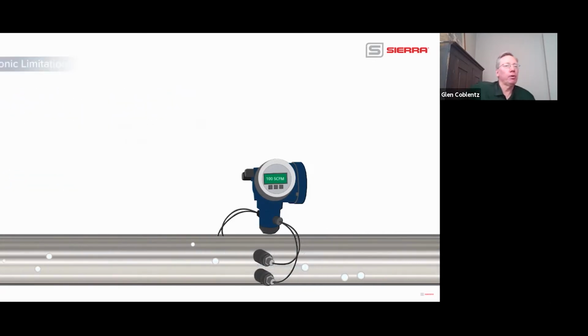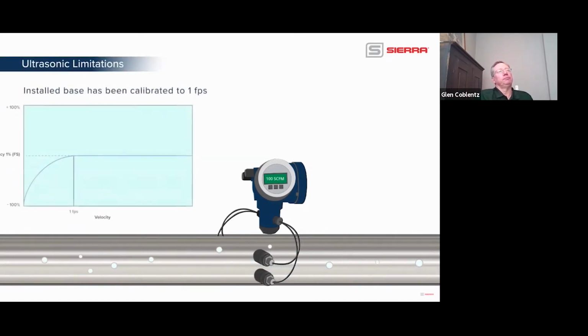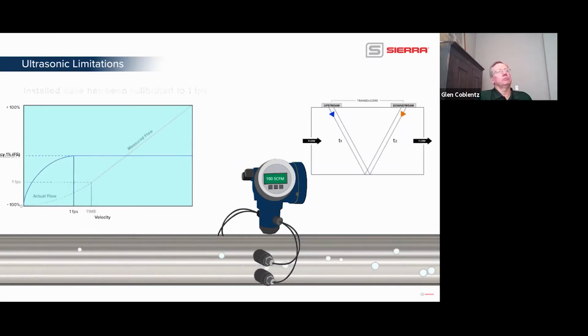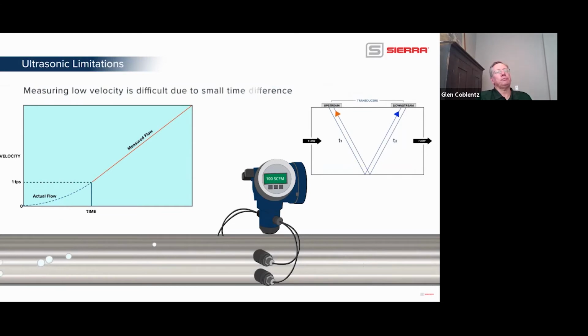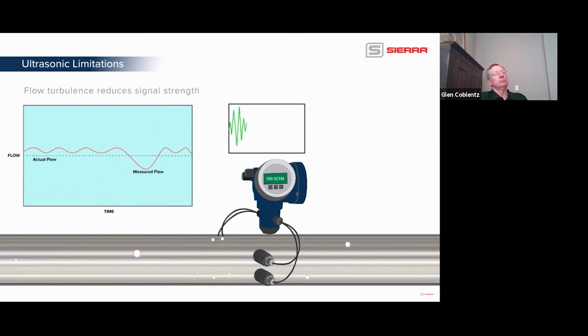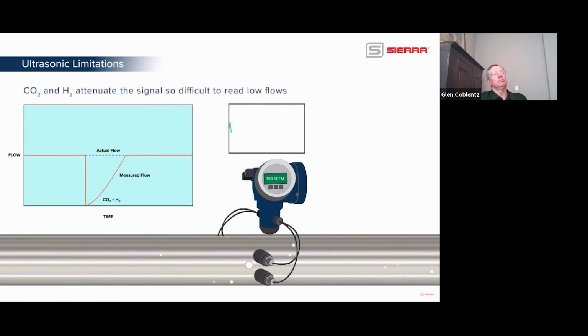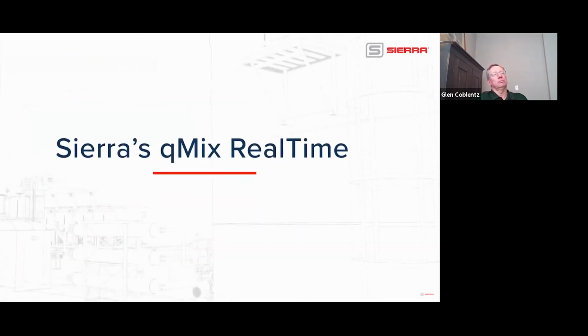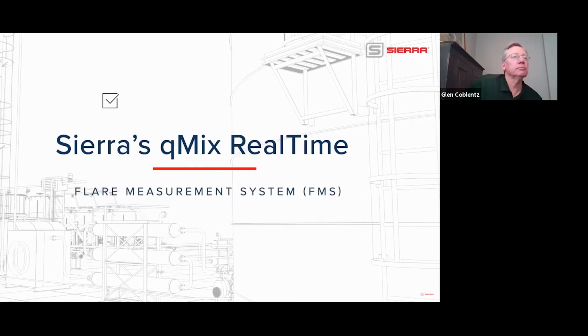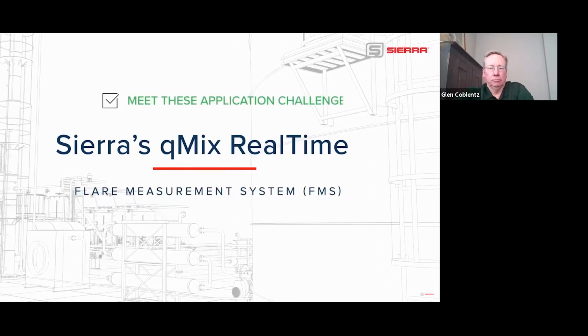But now, with the new low-end requirement, ultrasonic meters have the following limitations. The large installed base has been calibrated to 1 foot per second, so they can't meet the low end of the regulation. Measuring low velocity is difficult due to a small delta T. Flow turbulence reduces signal strength, and typical flare gases like CO2 and H2 attenuate the signal, so it's difficult to read low flows. Sierra's QMix Real-Time FMS meets these application challenges.